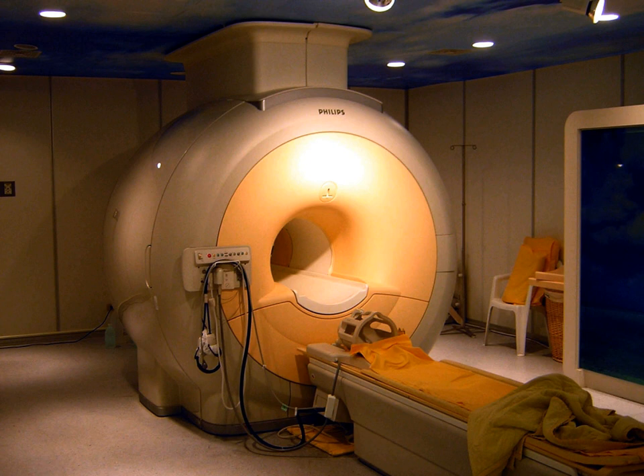Due to the magnetic Lorentz force from B0, the current flowing in the gradient coils will try to move. The knocking sounds heard during an MRI scan are the result of the gradient coils trying to move against the constraint of the concrete or epoxy in which they are secured. These sounds can be very unnerving to the patient, particularly given the tight space in which the patient lies. This behavior of MRI scanners can be described in terms of a fully coupled acousto-magneto-mechanical system. Solutions to such systems can provide useful insight for design engineers.